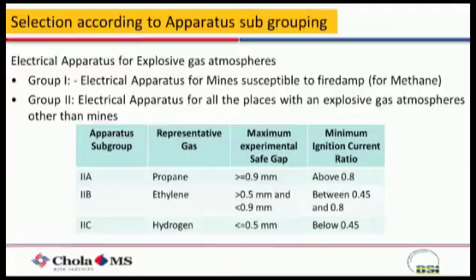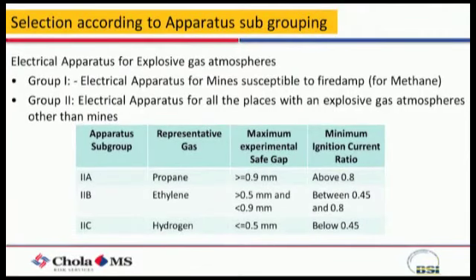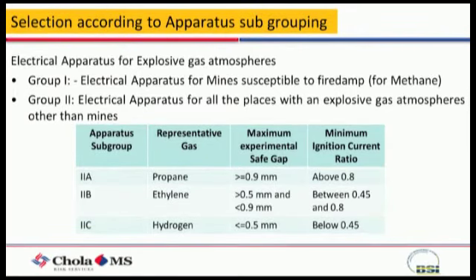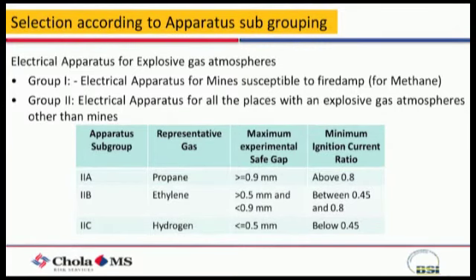That cool air, when it comes out of the enclosure or electrical fitting, is not going to create any hazard to the surrounding area. So enclosures are made to contain a small explosion within themselves. Like any normal domestic switch, there will be a small spark. Likewise, within the enclosure there will be a cable coming in, termination, and a small spark might come, but it will get quenched inside the housing itself. So these are gaps which are specifically to be maintained. It's not that I bought material with a 0.9 mm gap pertaining to gas group 2A and use this product in a 2C area.